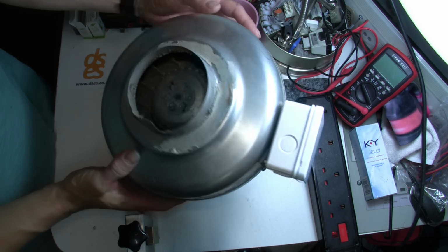Okay, after the self-test ends, all accessories are off. Flicking either light switch causes the fan and associated light to come on. Only when both lights are extinguished does the timer start. This is currently set to minimum time, so should hold the fan on for about a minute past lights out. This stop clock, you perhaps can't see, will tell us how long it's on for.